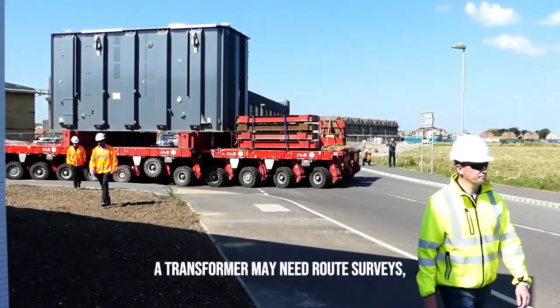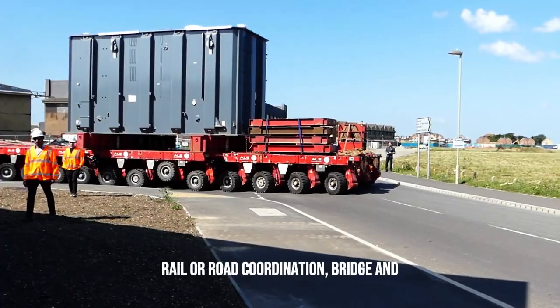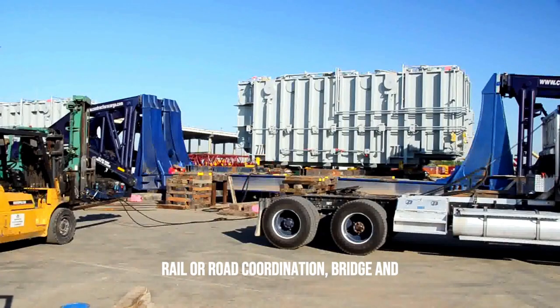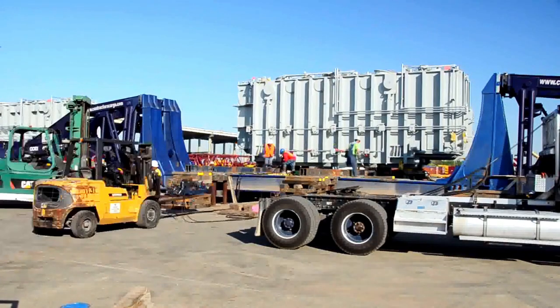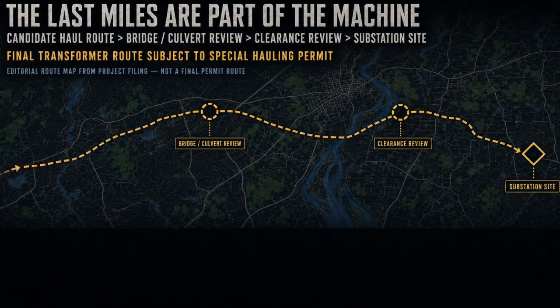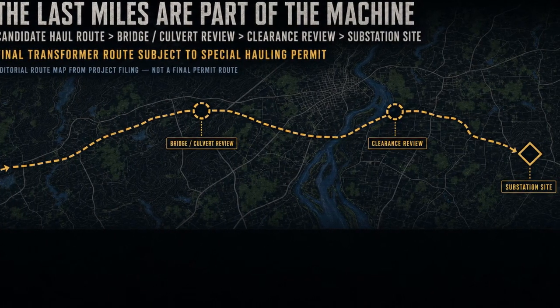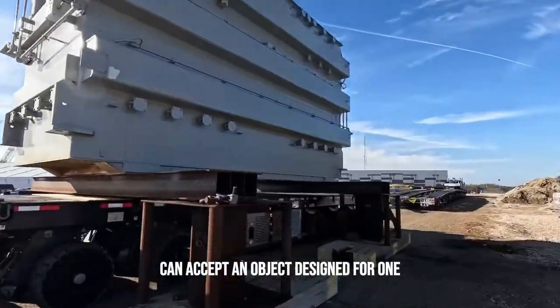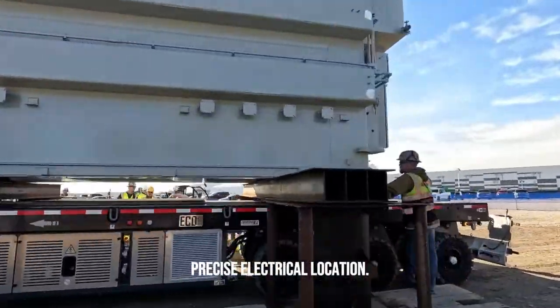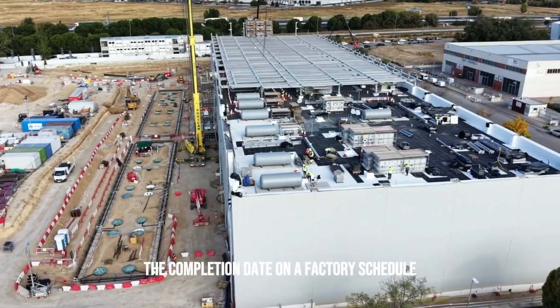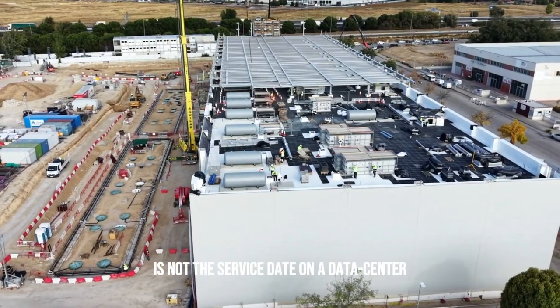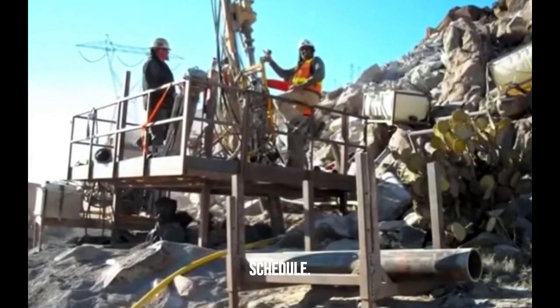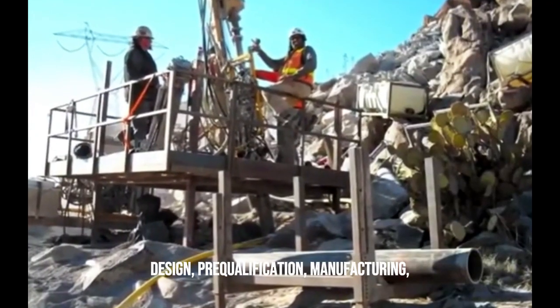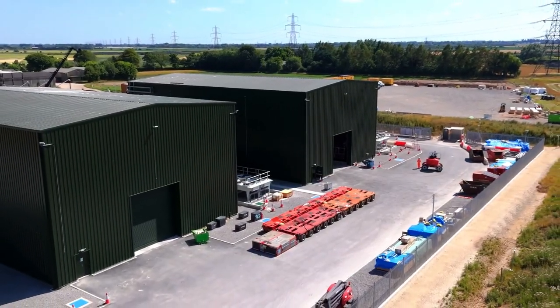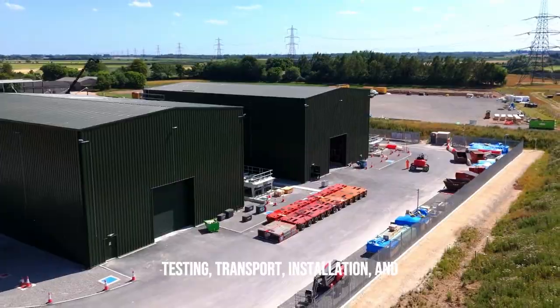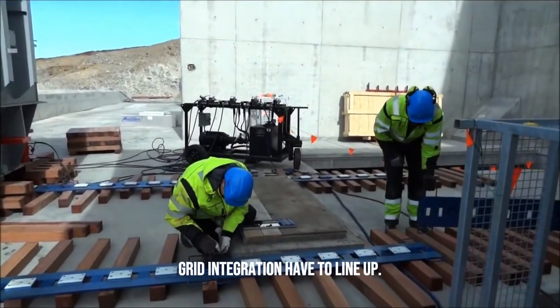A transformer may need route surveys, rail or road coordination, bridge and clearance checks, port handling, and a timed move into a substation. The obstacle is whether the destination can accept an object designed for one precise electrical location. The completion date on a factory schedule is not the service date on a data center schedule. Design, pre-qualification, manufacturing, testing, transport, installation, and grid integration have to line up.